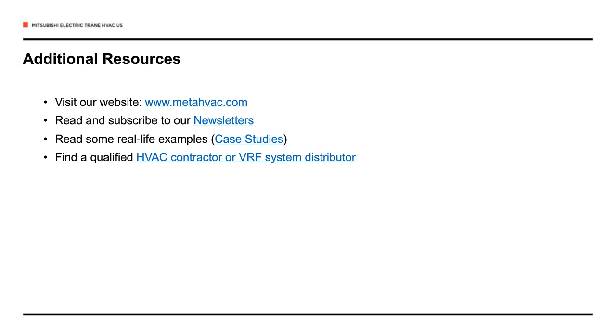So generally, for unit heater sizing, you can look at the total block heating load of the building and size the unit heater or unit heaters for that load, less any credit you would get from the VRF system. Generally speaking, your VRF system is going to be smaller because you're going to be switching over to that auxiliary gas heat at a certain ambient. And we've written sequences, and once again, this is covered in an application note that you can download on mylinkdrive.com that goes into these details.